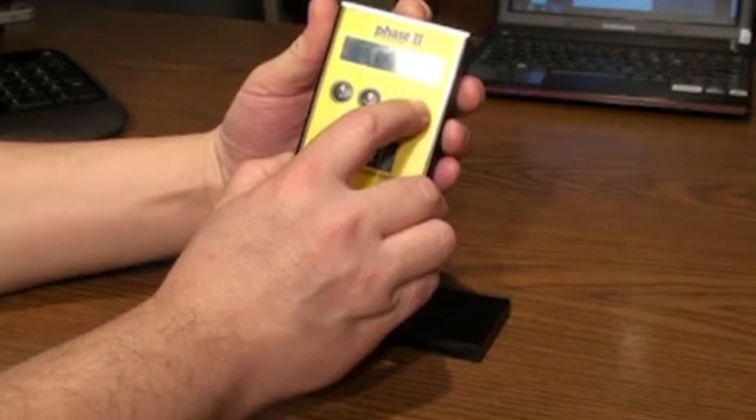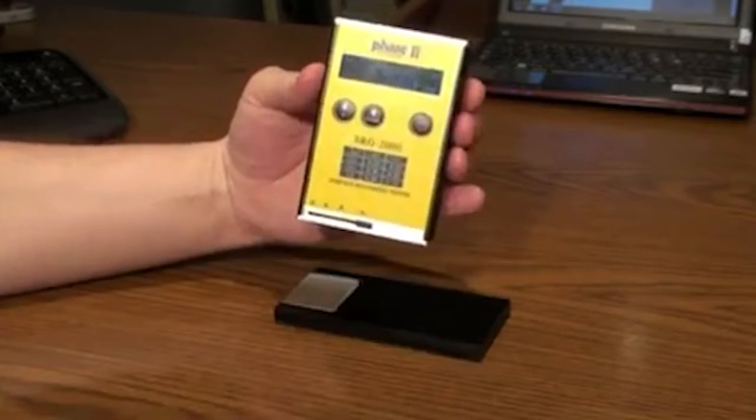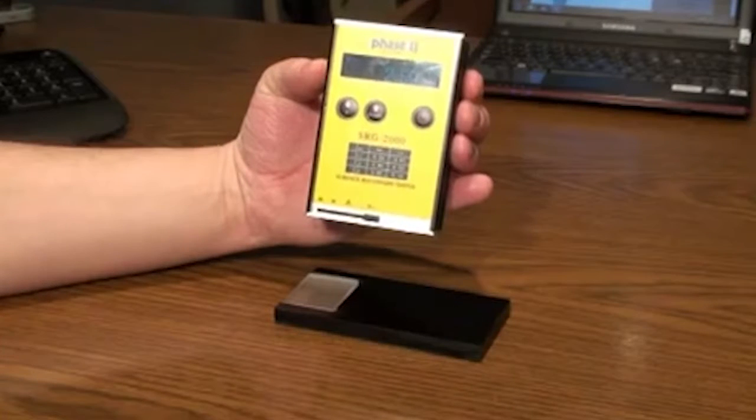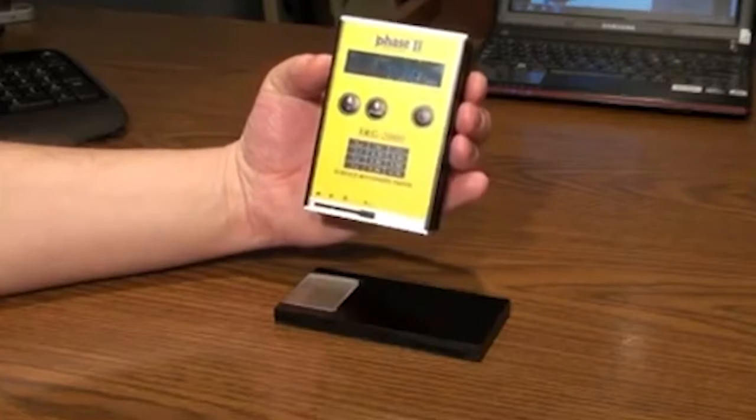When a beep sounds, release the button and the device enters its calibration mode. The LCD screen should read Cal and there will be an RA value on the display.